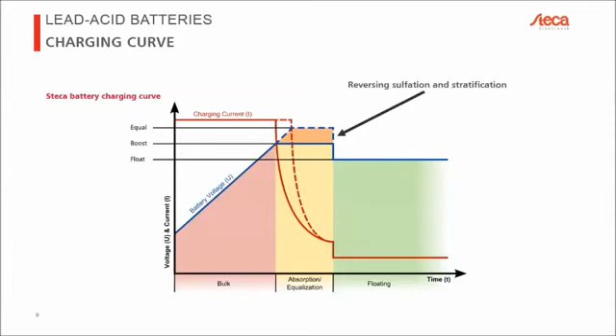What's important to know as well is that this phase, the boost and the equalization, is only for a certain amount of time. It's typically about 2 hours. That's to make sure that we have these positive effects, but that we're not losing too much water during this gassing process. Then the fourth point is do not exceed C5 or C10 currents for solar batteries. It means that for the capacity printed on the battery, don't discharge or charge with more than 1/5 or 1/10 of that capacity. So in the case of a 100 amp hour battery, 1/5 is 20 amps and 1/10 is 10 amps.